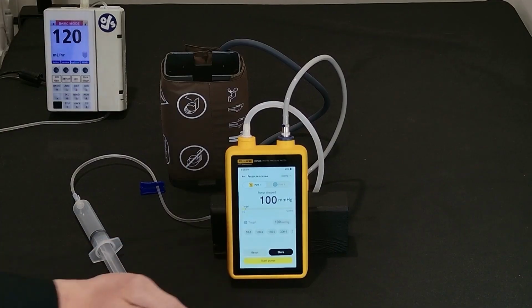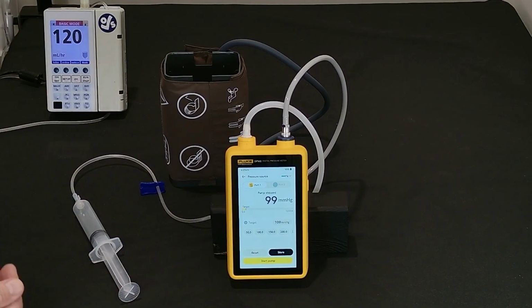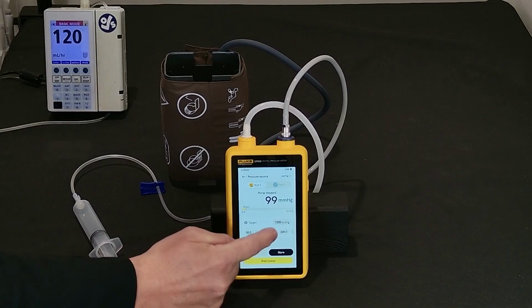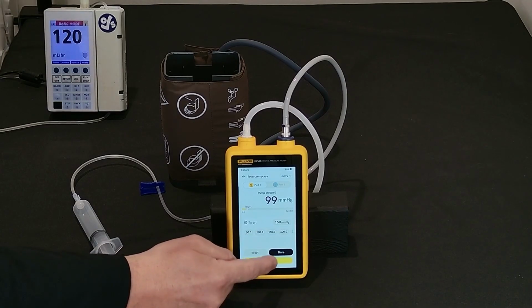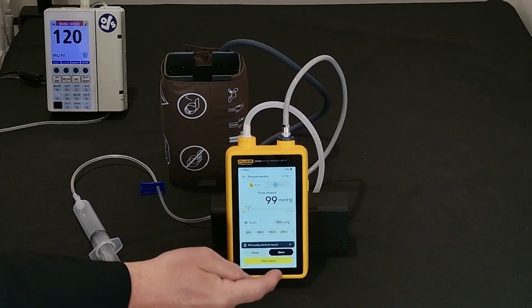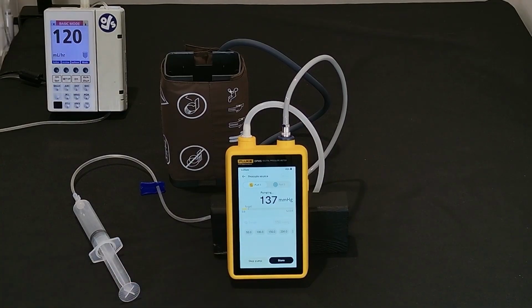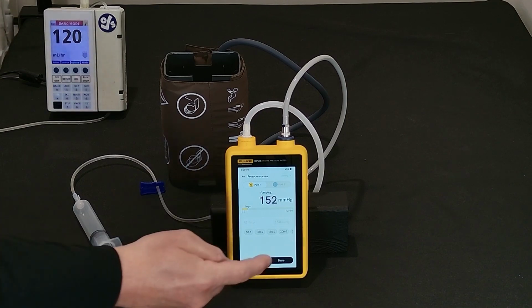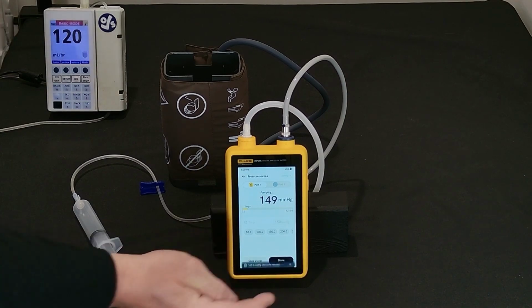You can stop your pump, select a measurement that is higher or lower. Here we'll just go higher, and then we can store that measurement, and then we can start the pump, and now you can see it goes up to the higher value. It stabilizes the pressure. Now it's holding the value. We can store, as always, store your measurement.